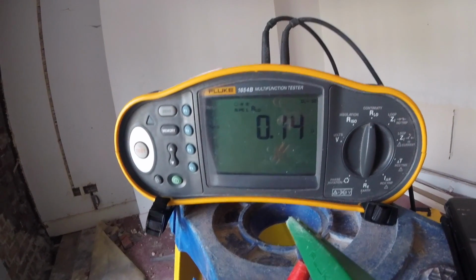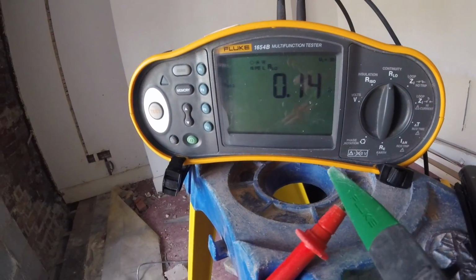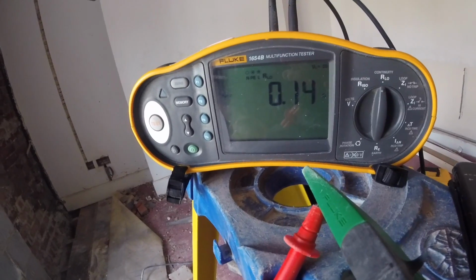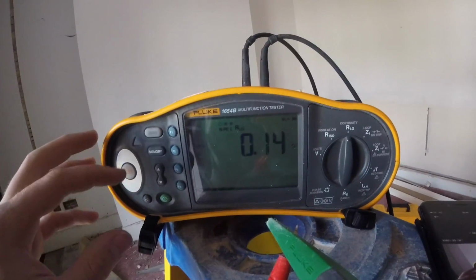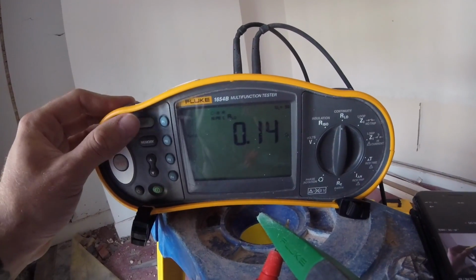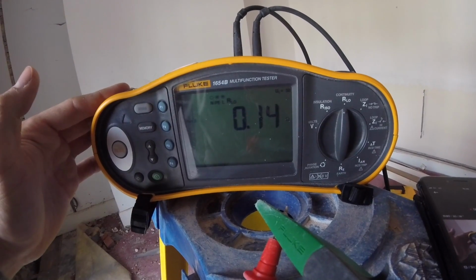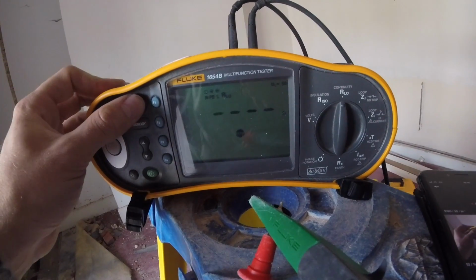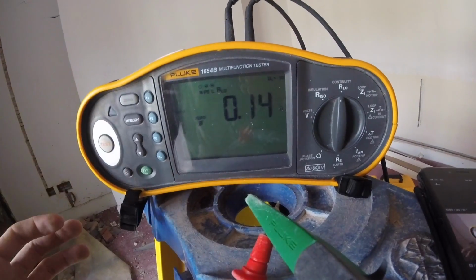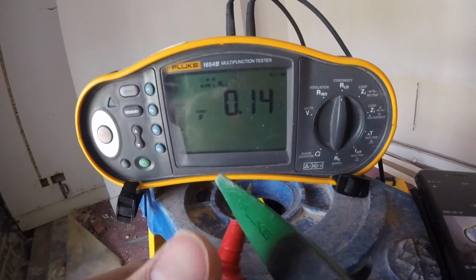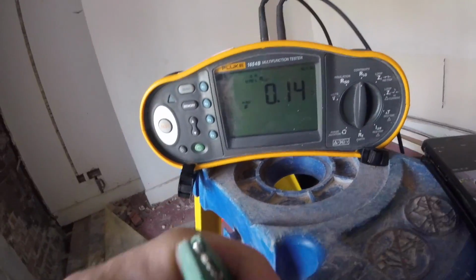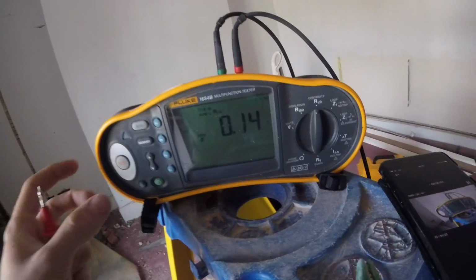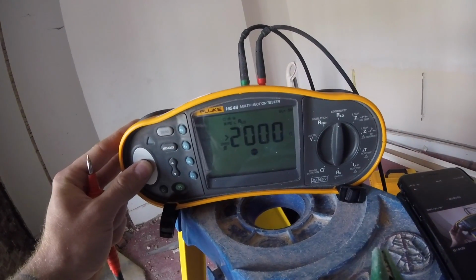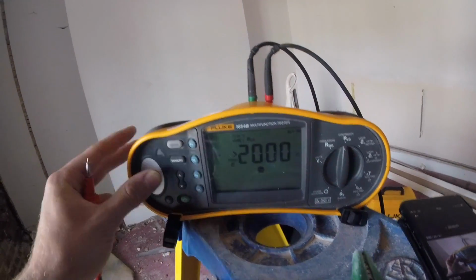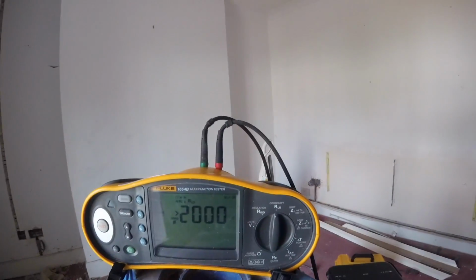But obviously before you do any testing, you want to zero the leads just to make sure your tests don't include the resistance of the leads. So all you need to do on this machine is hold down 0. That will quickly measure that, and that will take it into account when you take your readings. So now if I press test, greater than 2000 ohms, because they're obviously separated. So that's that test.